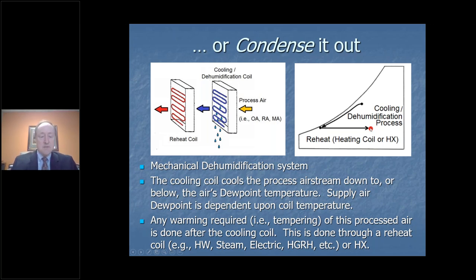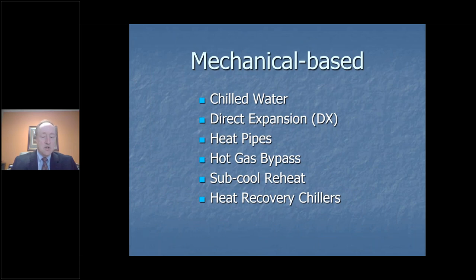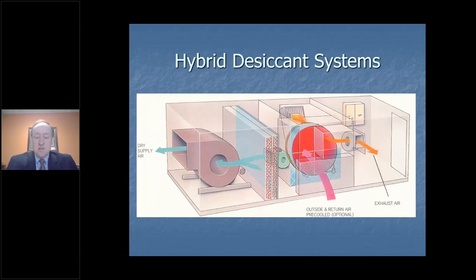There are a lot of different types of mechanical systems and parts and pieces that you can add to them to make them more effective for humidity control. This is what I would refer to as a hybrid system, and this is what I've used on most all of the surgical suites that I have worked with. In this case, we're using the best of both worlds. Let's do what the mechanical system does very effectively and very efficiently, and reduce the moisture down to a particular dew point of the coils.